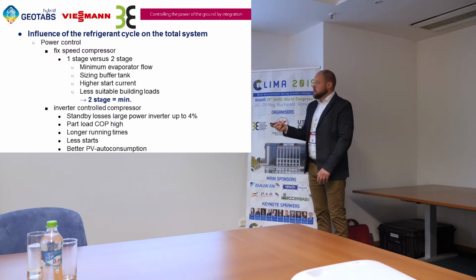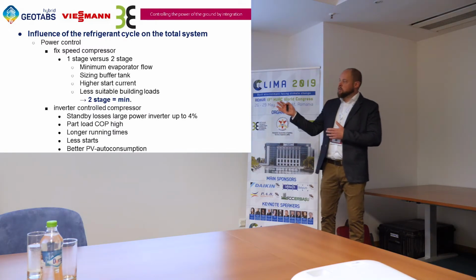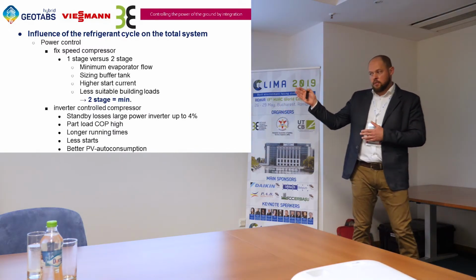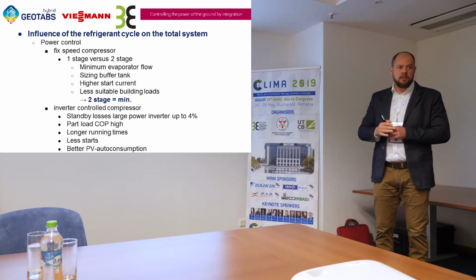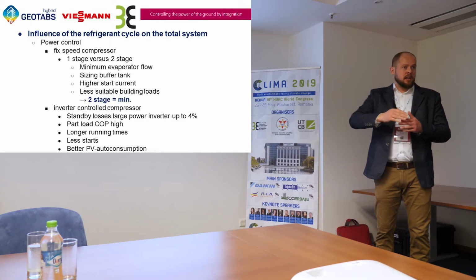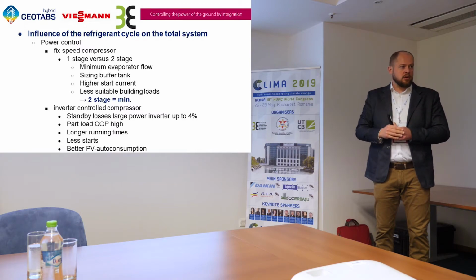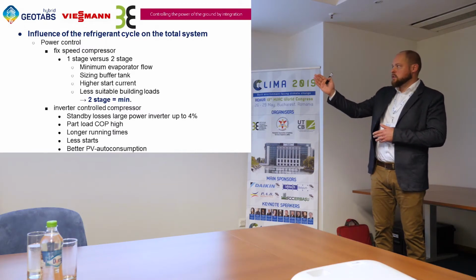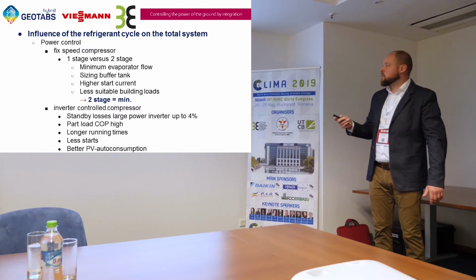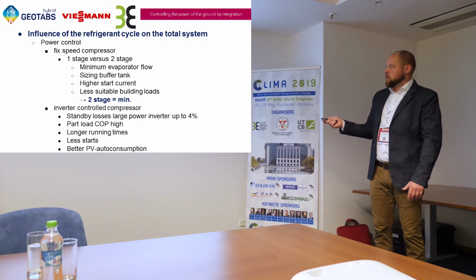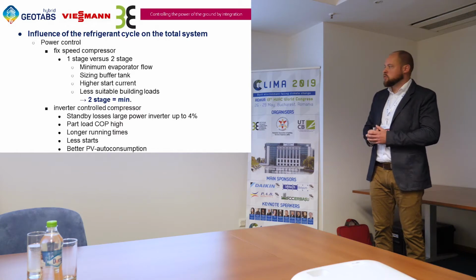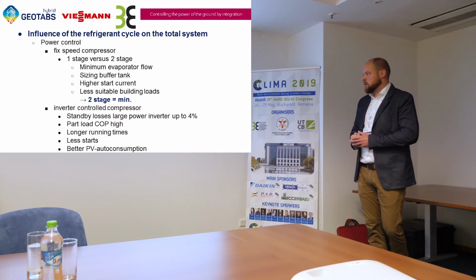It's less suitable for building loads, because, as you saw in the diagram in one of the first slides, with 40 or 50% of the power, we can almost cover the whole year. So you don't need 100% of the power that often. You will run more on the first stage of a two-stage compressor. So that makes it more suitable to follow the building loads.